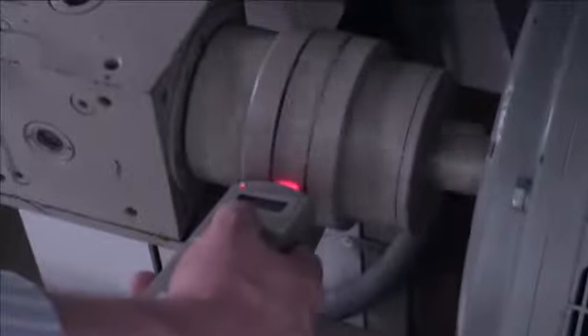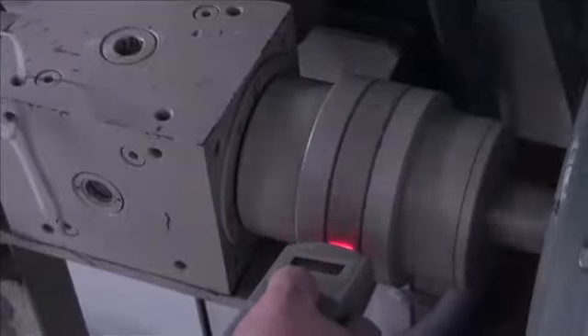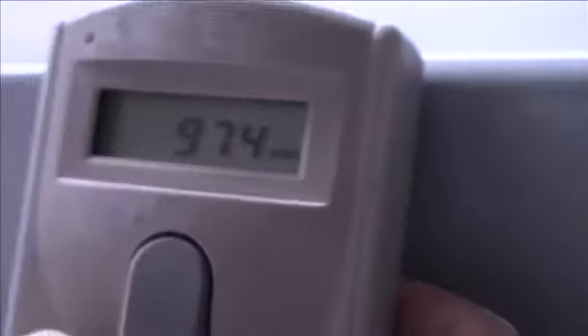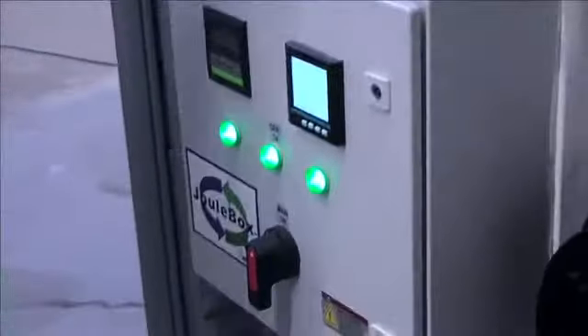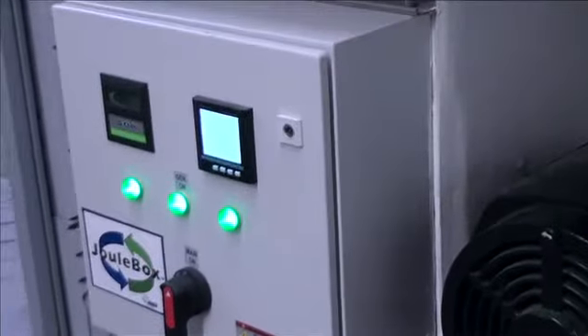I'm starting the blower first. As the RPM slowly increases from 615 RPM to 974, the power turbine is acting like a flywheel. We use this because it helps to stabilize the speed once the system gets up to speed. Because the JouleBox takes time to get up to speed, it should not be used as a backup generator. The JouleBox works best at full baseload power at all times. When the RPM gets over 1,000, we turn on the speed control motors to bring it up to 1,800 RPM. I turn on the power queue so we can monitor it by computer using the IP address.